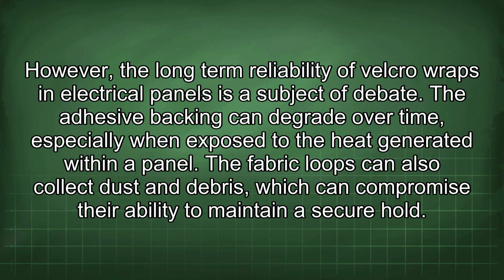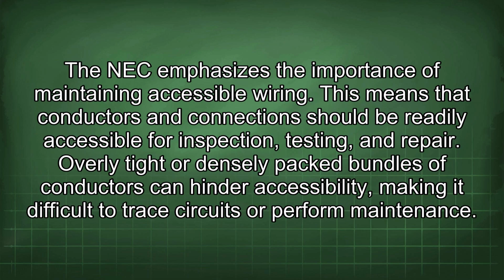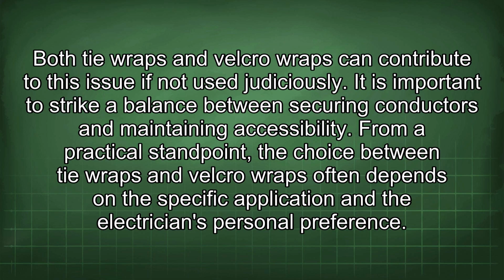However, the long-term reliability of Velcro wraps in electrical panels is a subject of debate. The adhesive backing can degrade over time, especially when exposed to the heat generated within a panel. Fabric loops can also collect dust and debris, which can compromise their ability to maintain a secure hold. The NEC emphasizes the importance of maintaining accessible wiring. This means that conductors and connections should be readily accessible for inspection, testing, and repair. Overly tight or densely packed bundles of conductors can hinder accessibility, making it difficult to trace circuits or perform maintenance. Both tie wraps and Velcro wraps can contribute to this issue if not used judiciously. It is important to strike a balance between securing conductors and maintaining accessibility.